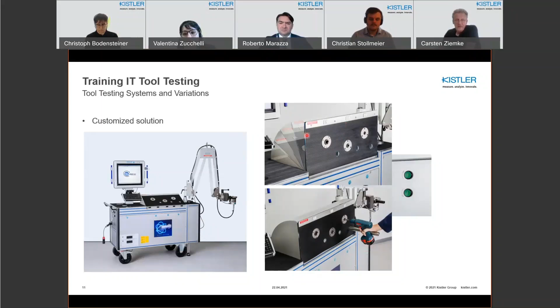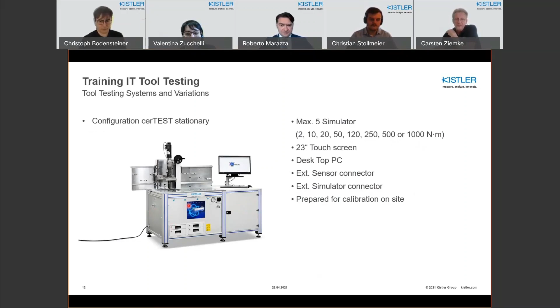The stationary system has 5 simulators here inside, and the biggest can be 1000 Newton meter. In this case, it's not necessary to have a special industrial PC - you have a standard PC here, including a touch monitor for easy use of the system. It's also possible to have an external connector for bigger simulators, and this system is also prepared for calibration on site.